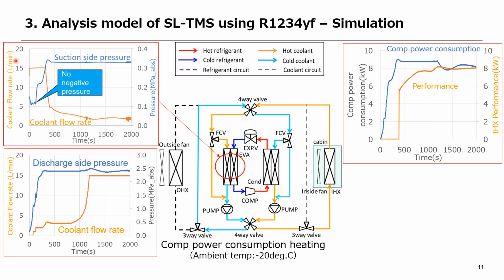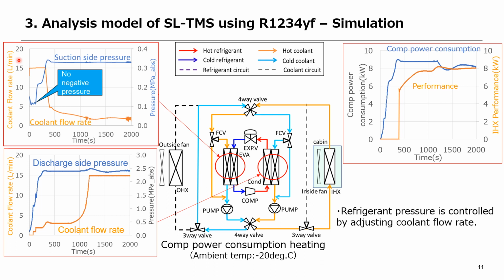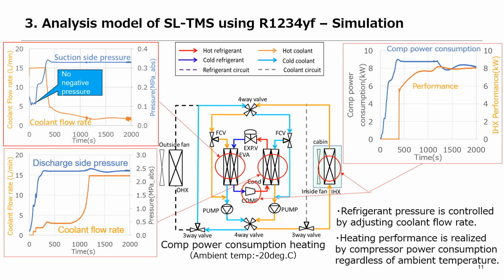From the lower left graph, if the condenser's high-side refrigerant pressure falls below the desired level, reducing the flow rate of cold coolant within the condenser can elevate this pressure. By further adjusting the coolant flow rate, the target pressure is achieved. Additionally, the right graph displays both the heating performance and compressor power consumption. As evident from the graph, the heating performance is consistently achieved through compressor power consumption, irrespective of the ambient temperature.